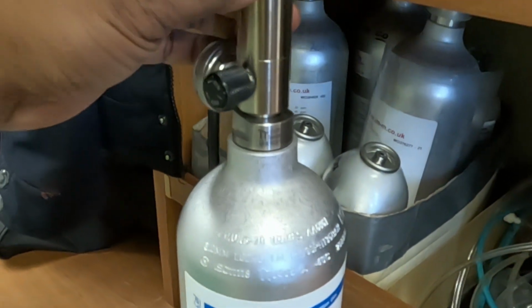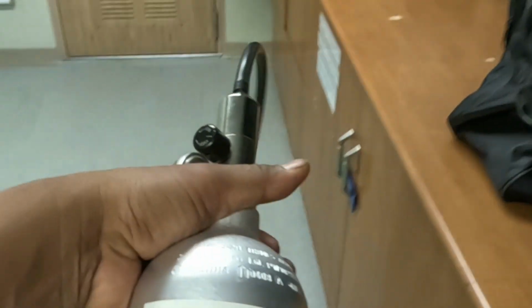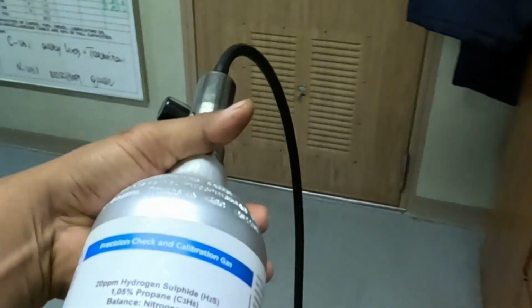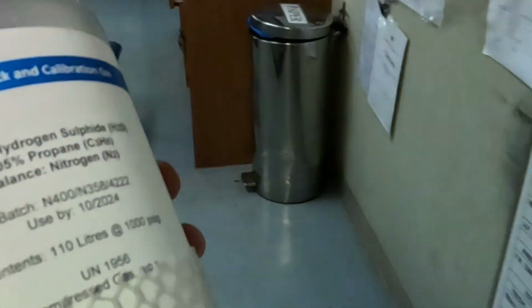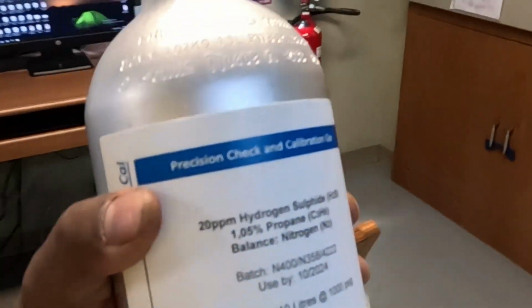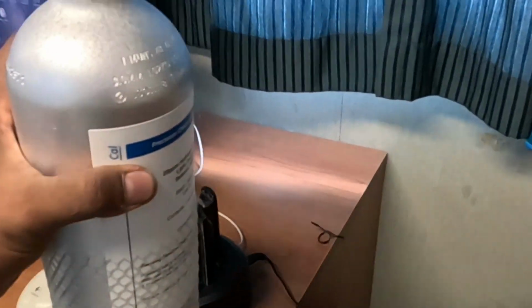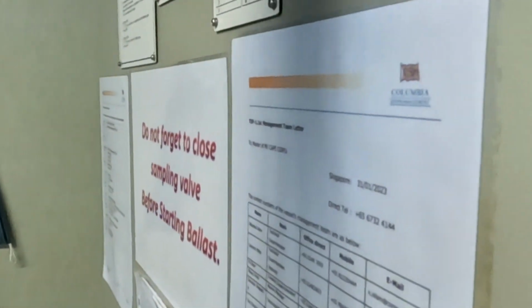You will introduce a gas containing H2S and flammable gas or LEL in order to simulate and trigger an alarm. In case it alarms, it means the equipment is working. That is one way to test if the sensors or the system is still functioning well.